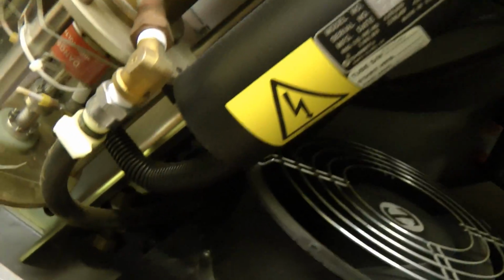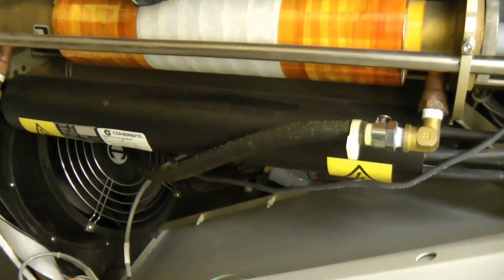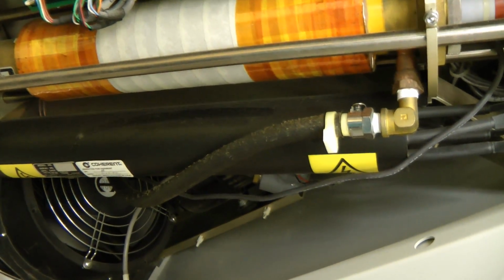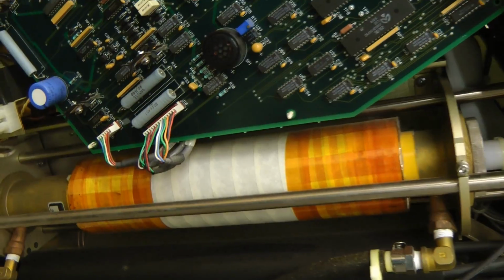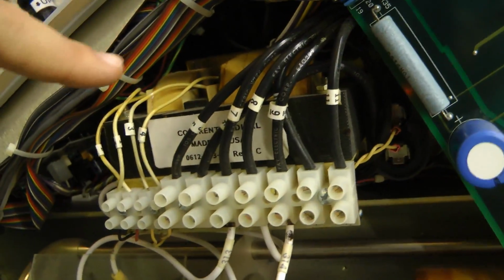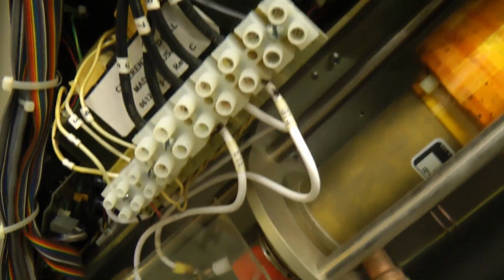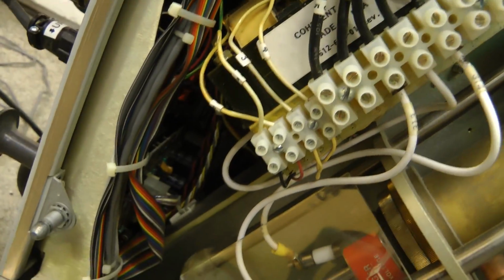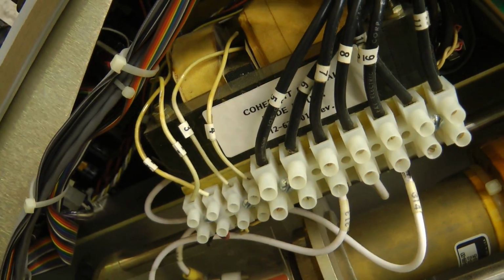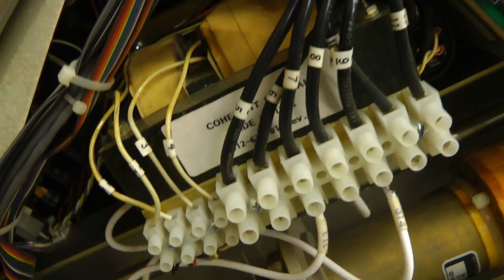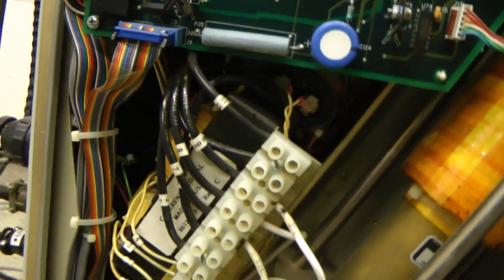And this thing off to the side seems to be connected down here to the gas fill port, so I'm thinking this is some sort of a gas reservoir. Not exactly sure why you need that, I guess due to expansion or something like that. Yeah, this is definitely the filament transformer. You can see the white wires from the filament running up to there. Oddly, there's a capacitor up here that's connected to the transformer. I wonder if they're doing some sort of resonant thing, because that's connected to the secondary and there's some shunts in there. Not sure what's going on there.